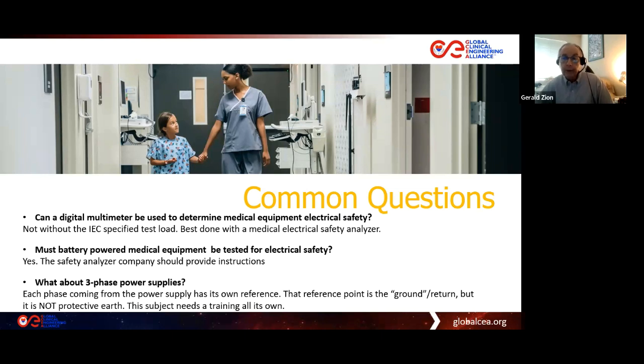What about three-phase power supplies? These are all the big iron things like imaging equipment, but also might be kidney dialysis systems that are powered by three-phase. One of the things we need to remember about three-phase power is that each phase coming from the power supply has its own reference voltage. They do not share a single reference point. They are the secondary of each of the phase transformers, and they power different parts of a larger system, like an X-ray room, a radiographic room, or a rad fluoro room.